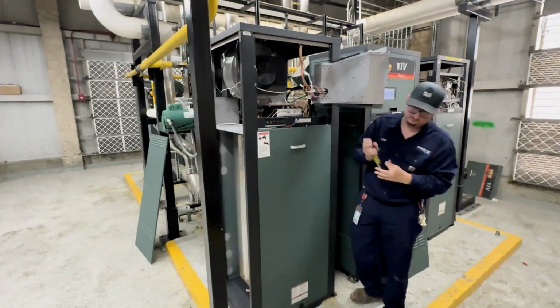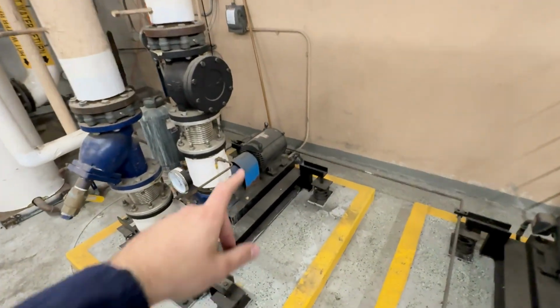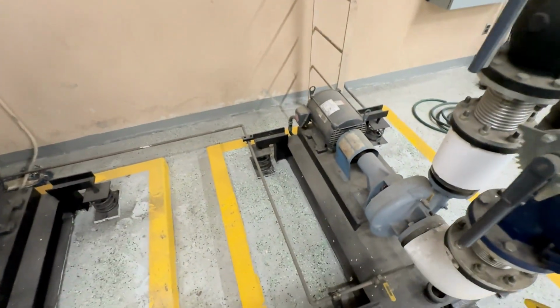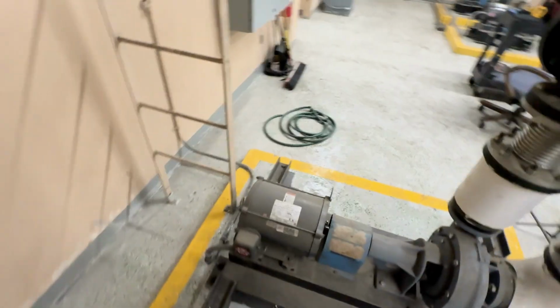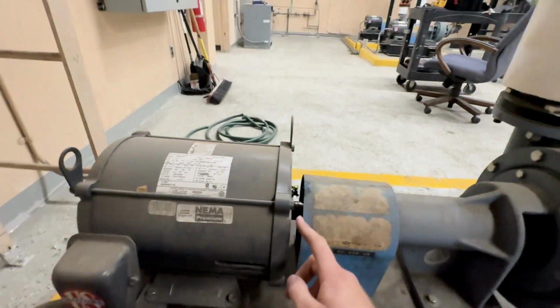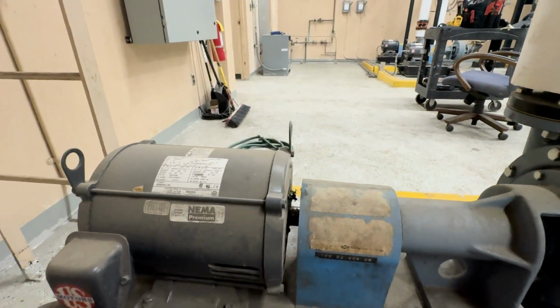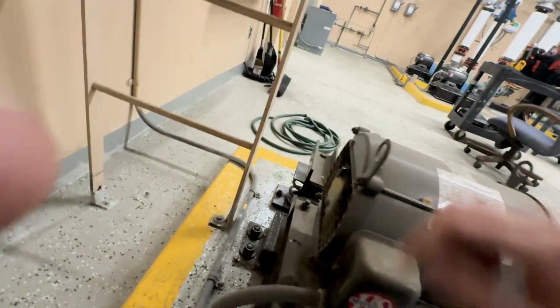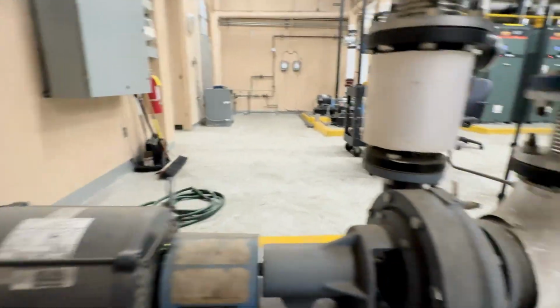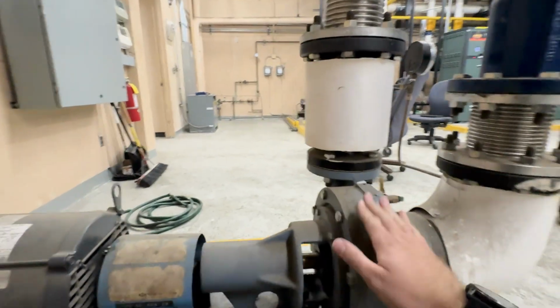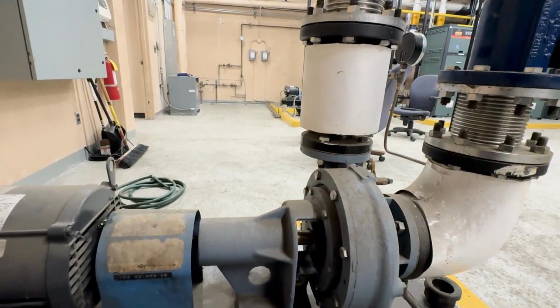While Tyler's finishing up taking off that panel, these are our hot water pumps for this system right here. I'm going to go ahead and grease the bearings and inspect them as well. They're shut off because there's not a call for heat, but the motor has a Zerk fitting right there for greasing, as well as one on the back. And then the pumps right here have sealed bearings, so there's no need to grease those.